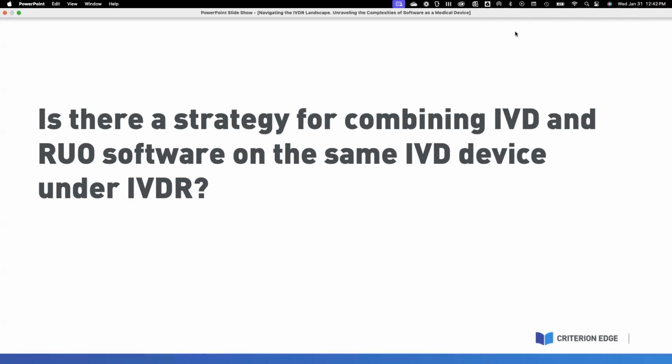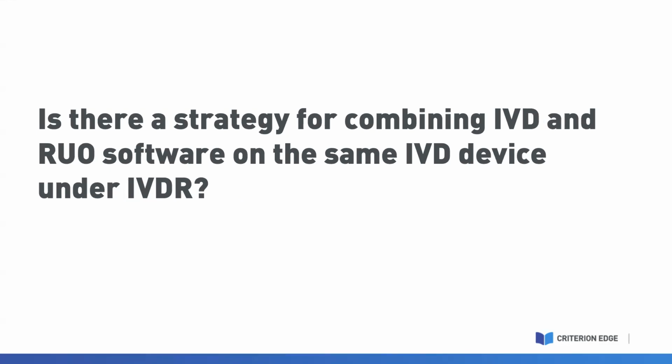Okay. Oh, so this is a fun one. The next question here: a strategy for combining IVD and research use only software on the same device. In a word, no, they don't really want you to be both. You are one or the other in the most classic sense. A research only device is not intended to be used with humans, and it's not intended to provide results to patients. So those would be used in more of an educational or laboratory-based setting.